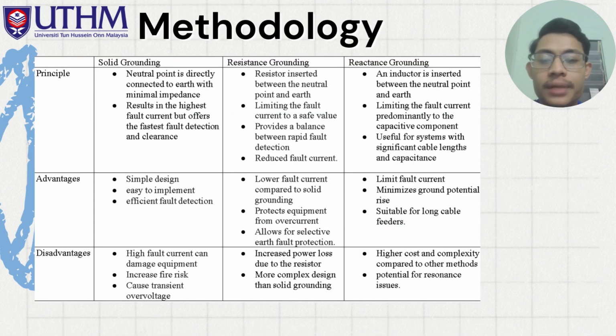Assalamualaikum, my name is Muhammad Faizal and I will present the methodology. On the slide are various types of neutral grounding. First is solid grounding. The principle is the neutral point is directly connected to earth with minimal impedance, resulting in the highest fault current but offering the fastest fault detection and clearance. The advantages are a simple design, easy implementation, and efficient fault detection. The disadvantages are that high fault current can damage equipment, increase fire risk, and cause transient overvoltage.